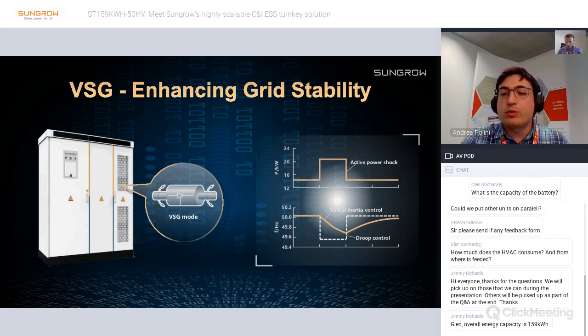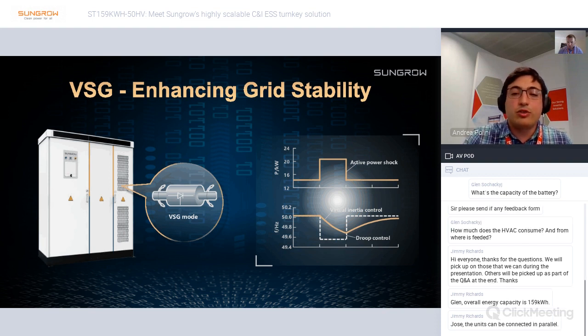The product can also be used in what we call the virtual synchronous generator mode. This operation mode allows the grid operator to use the ESS as an asset for grid stability. In fact, when the grid usually experiences a quick variation in load, this can generate an instantaneous drop in frequency. You can see it in the dashed line on the slide here. To avoid this, the ESS controlled in VSG mode will use the battery power to smooth the frequency variation using the virtual inertia control and the droop control algorithm. This results in a more stable local grid, which benefits, of course, the business operation of the customer as well.